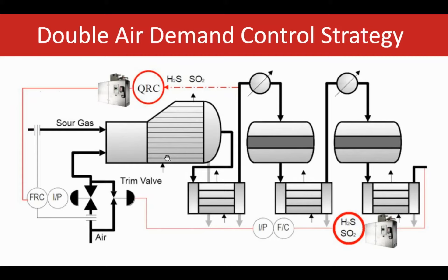Since the second analyzer is placed after the first condenser — the first being the normal tail gas analyzer already familiar in many plants — the analysis results do not depend on any complicated chemistry going on in the reaction furnace or on compositional changes in the feed gas. None of the limitations mentioned earlier about what technology can measure apply here, because everything is happening after the reaction furnace. The analyzer doesn't even see what is going on in the furnace, which eliminates many measurement limitations associated with specific species in the Claus process.